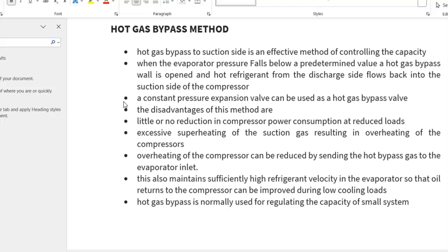Overheating of the compressor can be reduced by sending the hot gas to the evaporator inlet. This also maintains sufficiently high refrigerant velocity in the evaporator so that oil return to the compressor can be improved during low cooling loads. Hot gas bypass is normally used for regulating the capacity of small systems. Sometimes we have heard that if some oil remains in a layer inside the evaporator coil, how do you remove it? By supplying the hot gas.